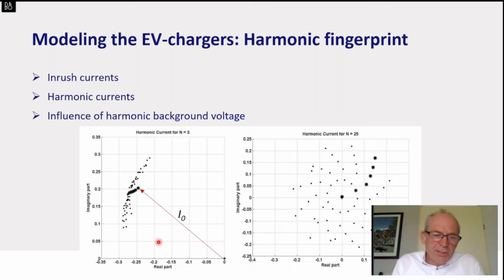What you normally will see is that, depending on the phase shift of the voltage and the current, harmonic background voltage could increase the harmonic current of the charger, but it could also decrease the harmonic current of the charger. These harmonic fingerprints are important to get some insight into how the chargers react to harmonic background voltage.